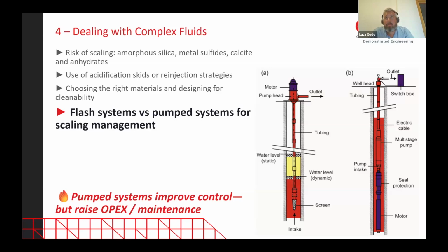I remember one example: you never use curved tubes in heat exchangers in binary systems, only straight tubes. But materials matter too — sometimes you need to select the right materials to allow cleaning, even chemical cleaning, because mechanical cleaning isn't always possible. Or, talking about corrosion rather than scaling, you'd need some corrosion allowance on your materials.